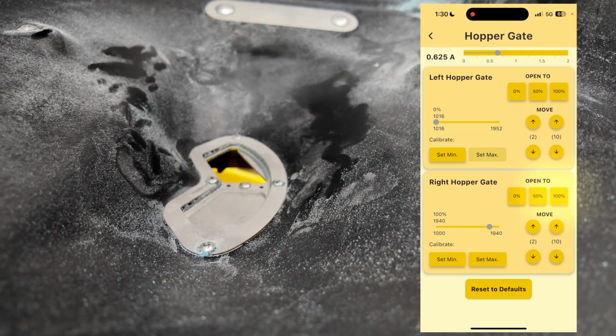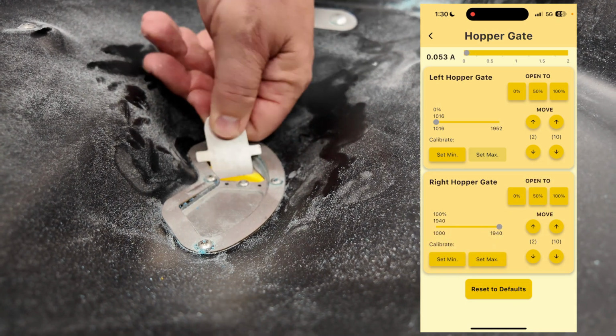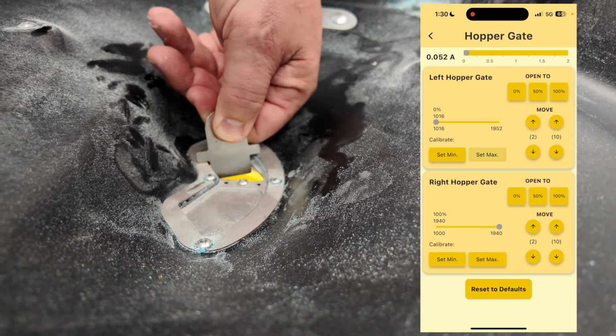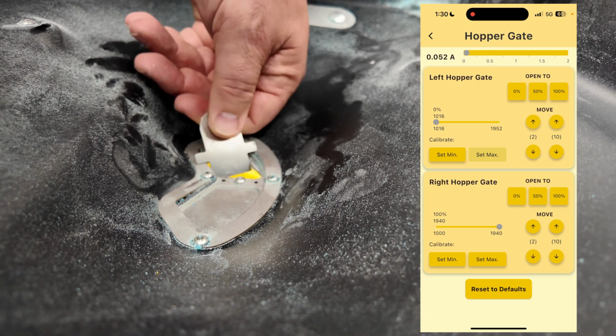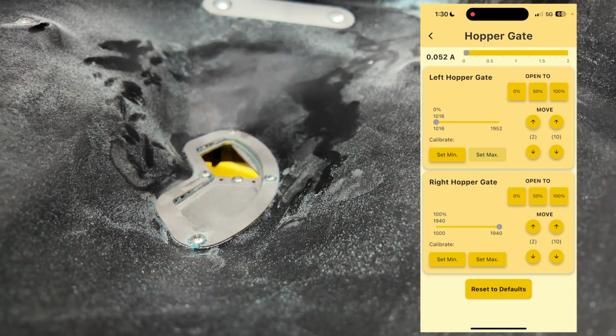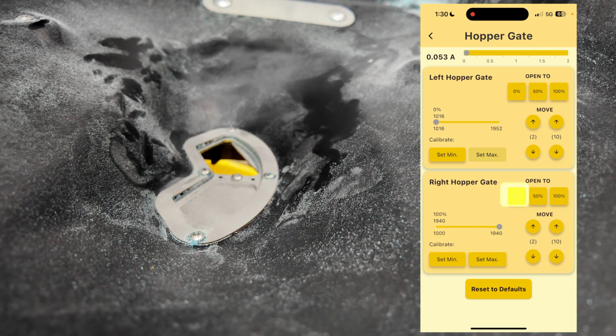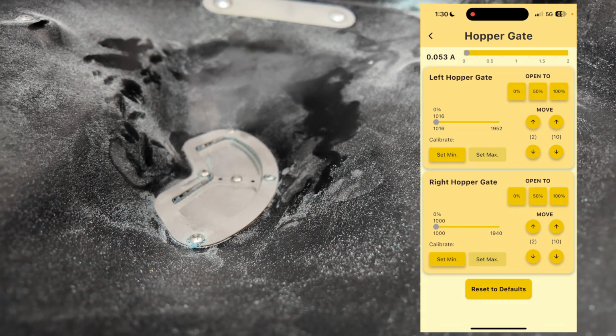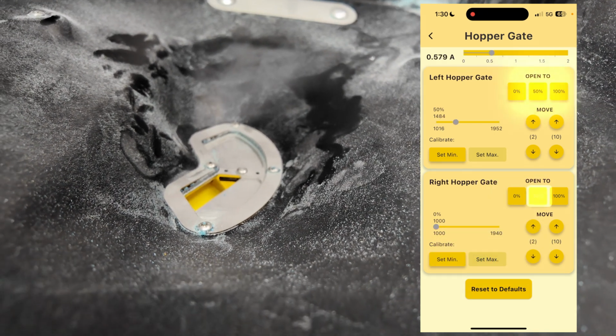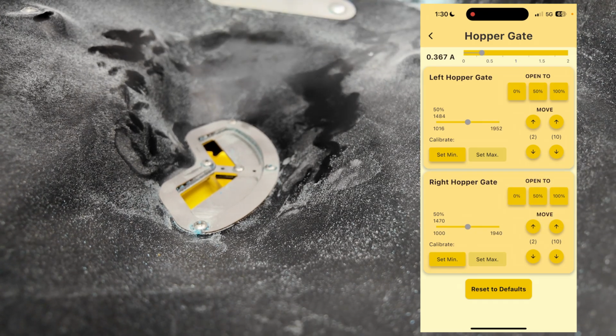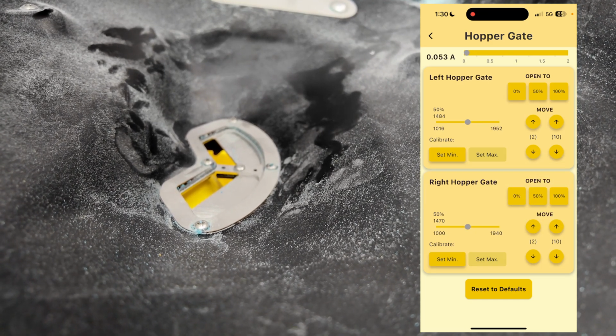Now I'll move it to 100%, turn it 90 degrees. Because I've already calibrated before, it's set perfectly. I'll hit set max. Now I've gone ahead and set the min and max position for the hopper gate. To validate it, I'll move them both to 50%, and I can look down at the top and see they're set exactly the same where they should be.